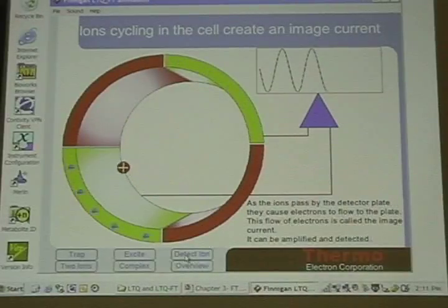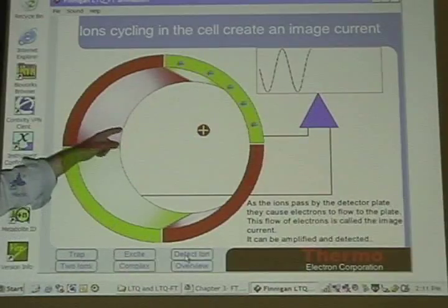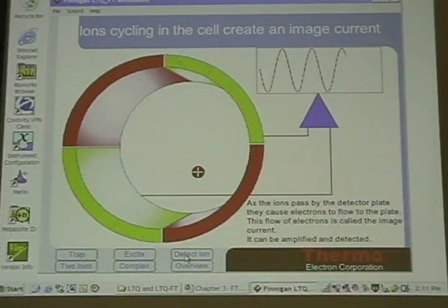On the FT, if I put 200,000 ions of a complex mixture, I get space charge. If I put 200,000 ions of one mass, I don't get space charge, because the one mass ions are always moving at the same frequency. They don't do the crisscrossing, so they don't space charge. Hypothetically, if there's 200,000 of the same mass, some of them are going to be riding on top of each other. They're close, but they don't space charge. It's only when they pass each other by, and you create that little RF type experience.